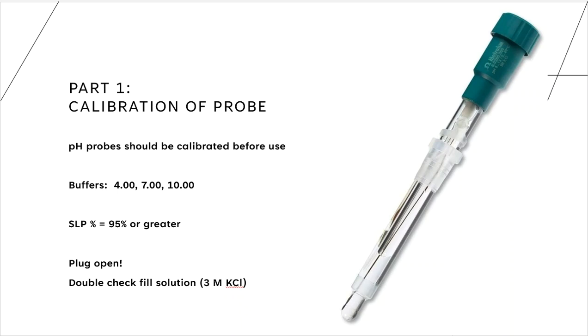And the first part is the calibration of the pH probe. So just like when we use a pH meter in a lab setting, we're going to have to calibrate the probe before we use it and before we titrate anything at all. So that's why this is step number 1. And in order to calibrate a probe, we have to use 3 buffers most of the time. So those are buffers 4, 7, and 10.